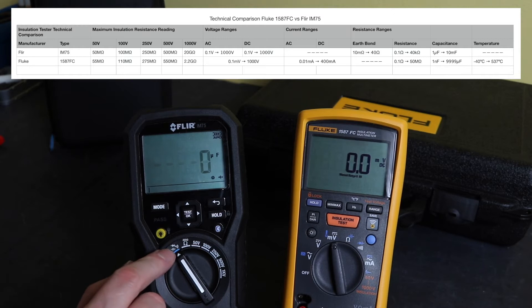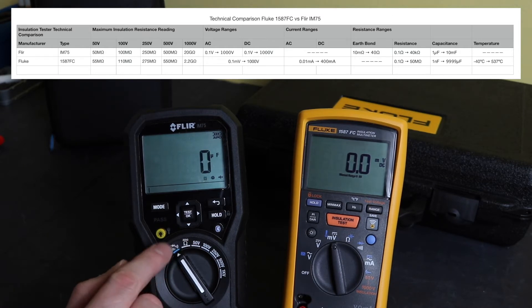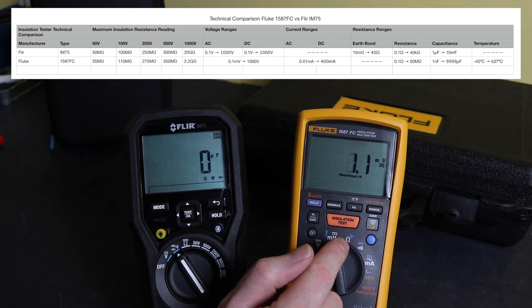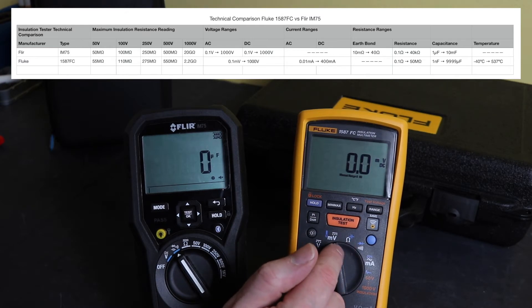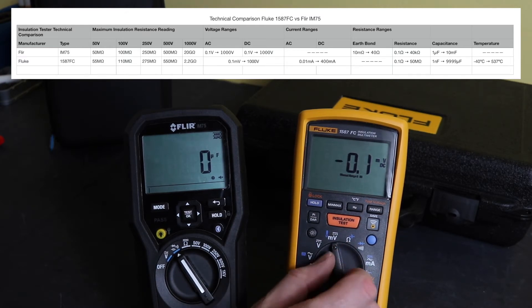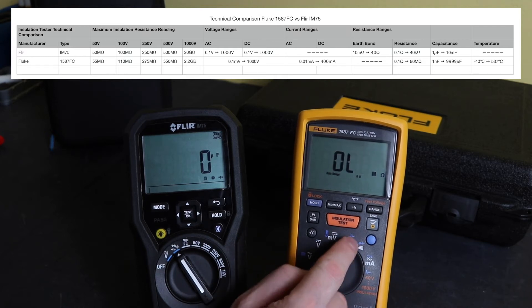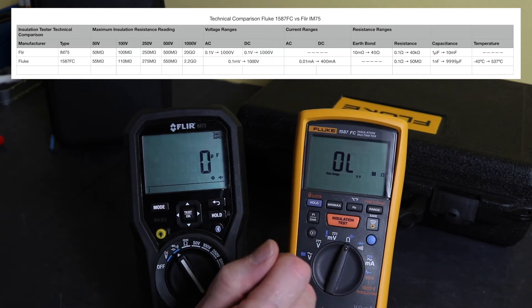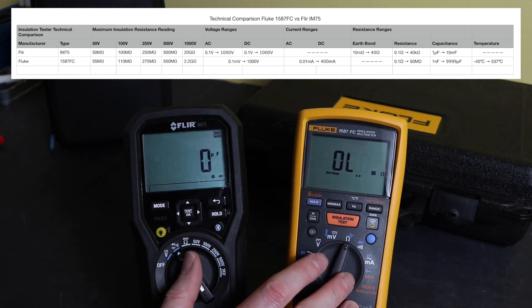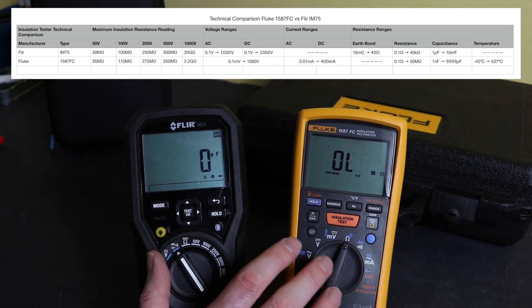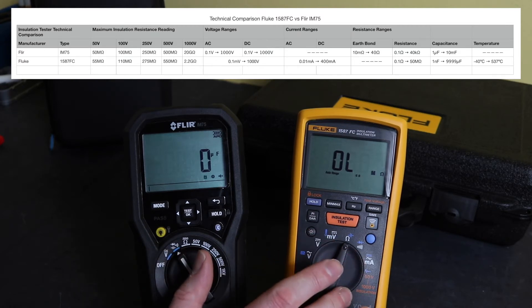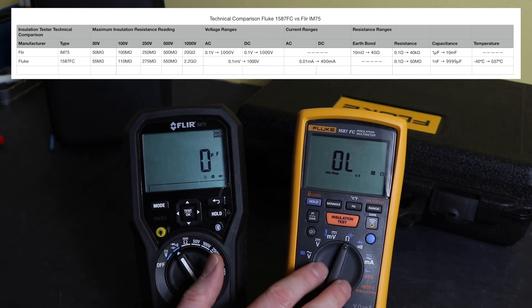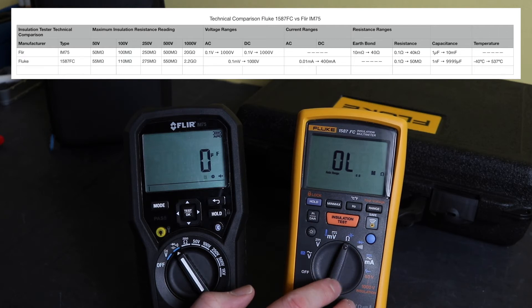And the next position on the Flir is diode, continuity, and capacitance. For the 1587 here, those two functions are split across two positions on the rotary switch. First position you've got the ohms and the capacitance, and second one you've got the diode and the continuity. Capacitance on these two instruments, one microfarad to 10 millifarads on the Flir, one nanofarad to 9.9 millifarads on the Fluke there. So a bigger range available on the 1587.